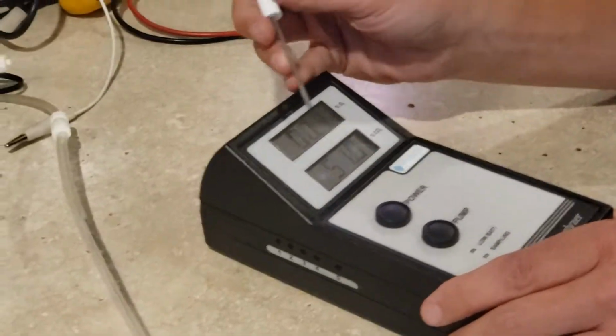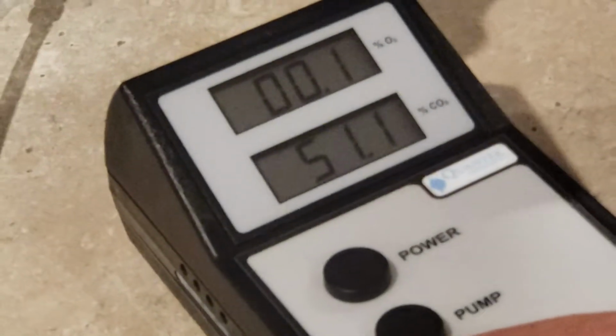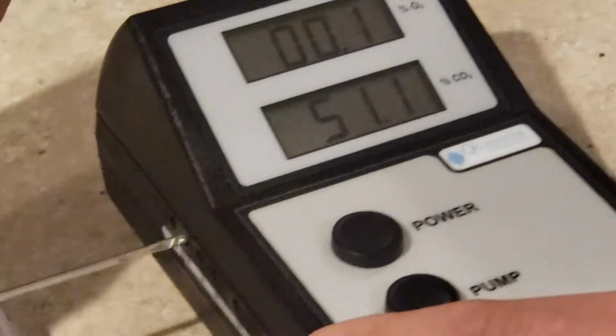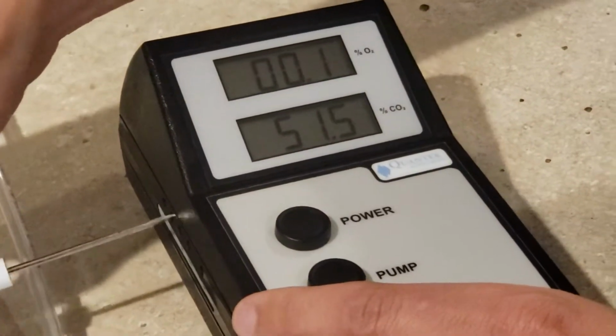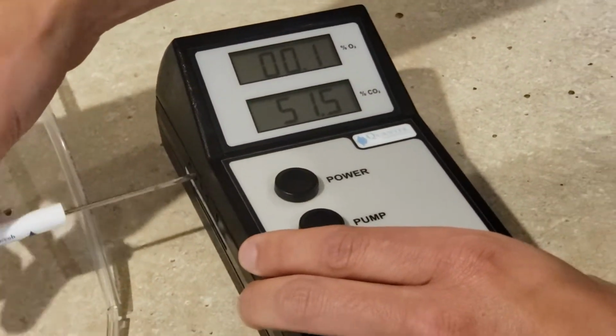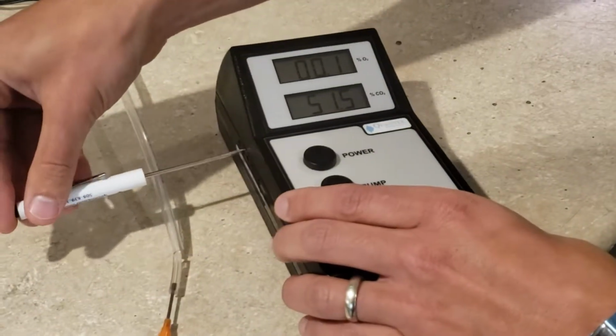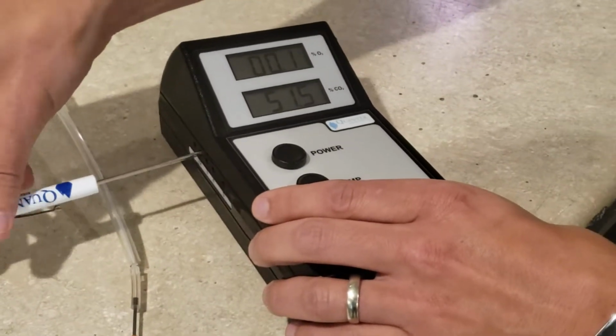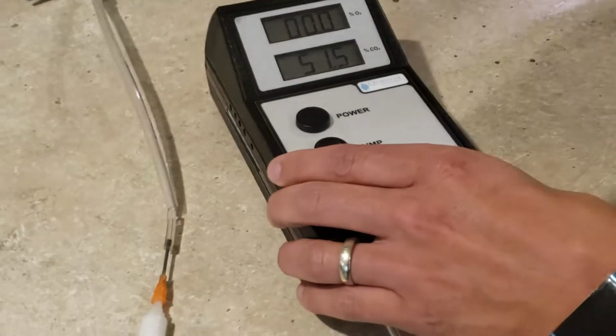Okay, great. So if we look at the oxygen reading, it should be reading 0. It's reading 0.1. If I wanted to adjust that, I would go to the second potentiometer here on the side. This is the 0 adjust for the oxygen. And if I wanted to go up, I can turn it like that. And if I wanted to go down, I could turn it like that. So in this case, I'm going to set it to 0.0, which is where it should be.